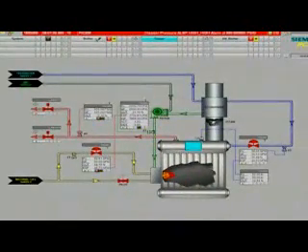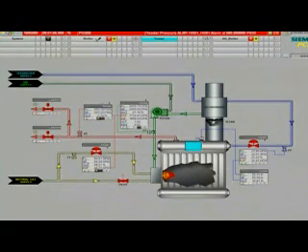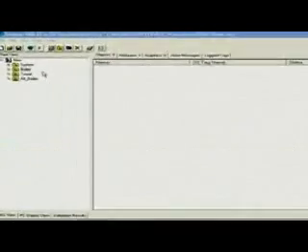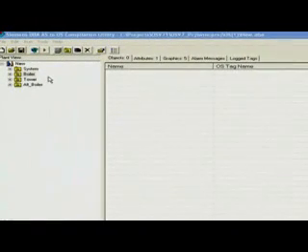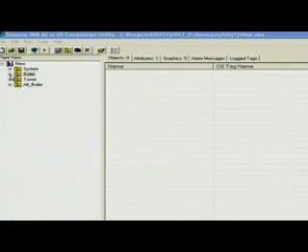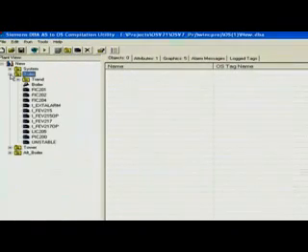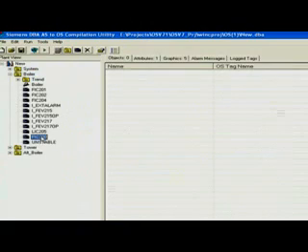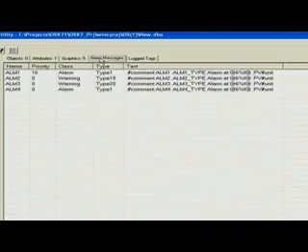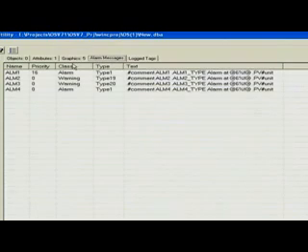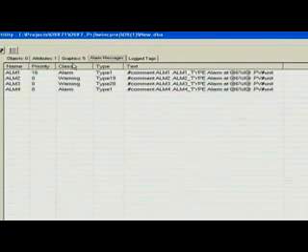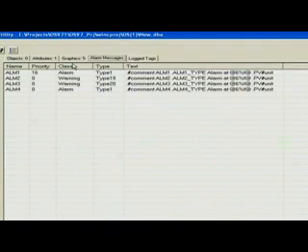You can also change the alarm priority. For example, from DBA, expand the plant view and select the object to be edited. For this example, I have selected PIC 200. The alarm tab allows you to set the alarm priority for each alarm. This information does not exist in the APACS alarm block, but is very helpful in managing system alarms.